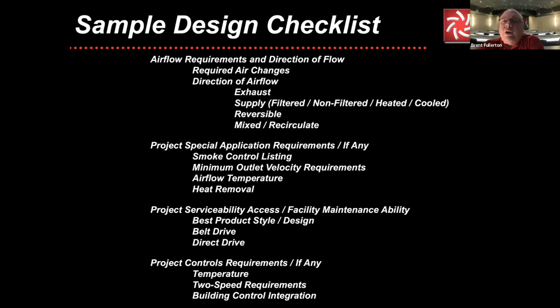First off, the airflow requirements and direction of flow. Well, you've heard it from some of the other speakers today. What are your required air changes? And also, what's the direction of flow? Is it exhaust? Is it supply? If it's supplied, is it filtered? Does it have to be filtered? Can it be non-filtered? Can it be heated? Can it be cooled? What about reversible applications? There's a lot of time that reversible applications are very, very beneficial.